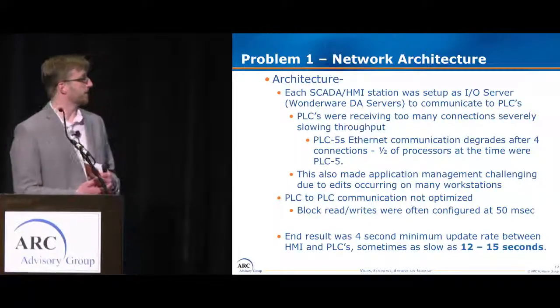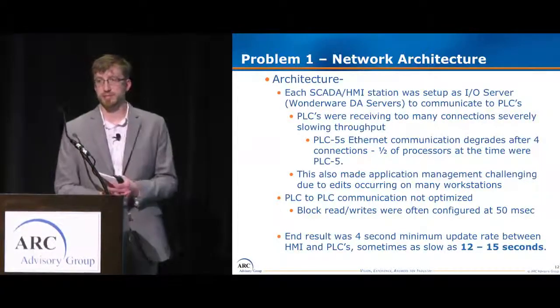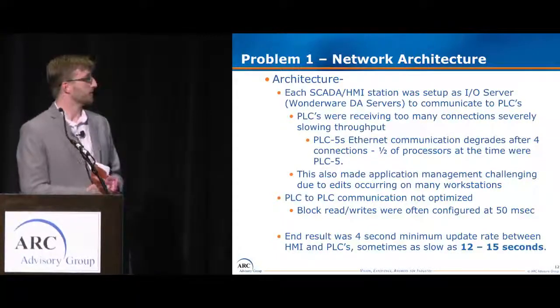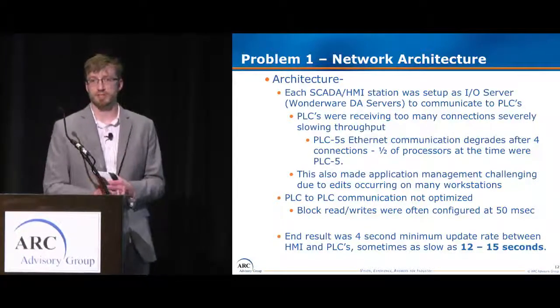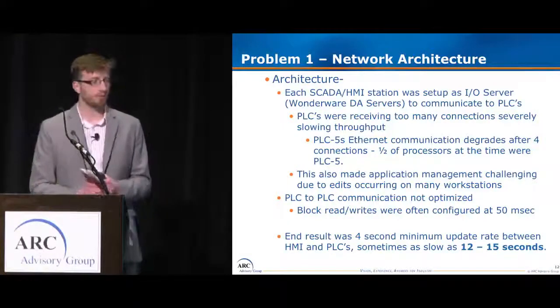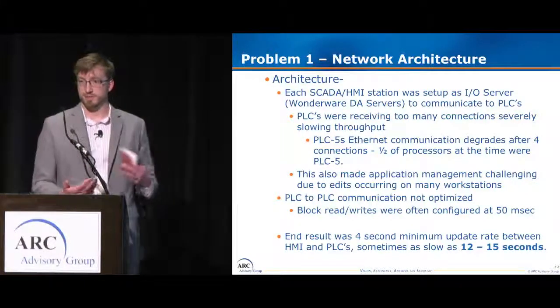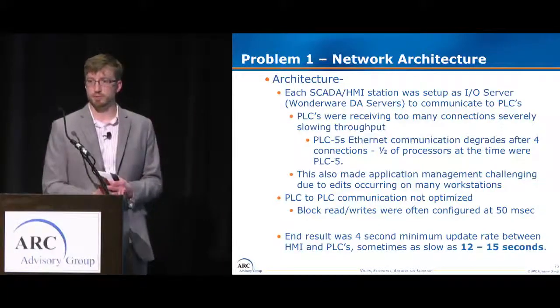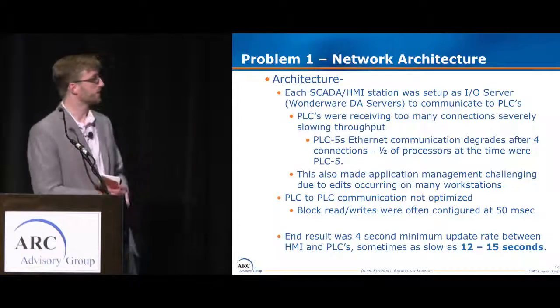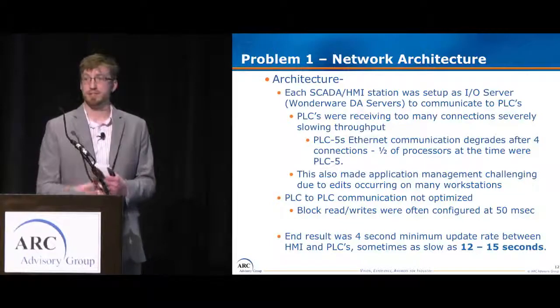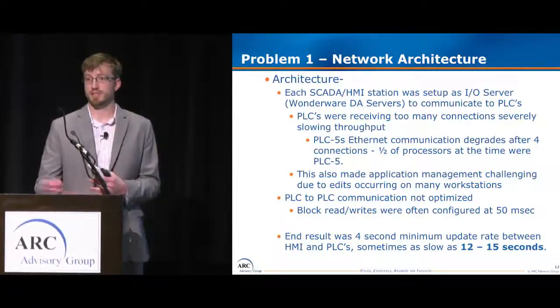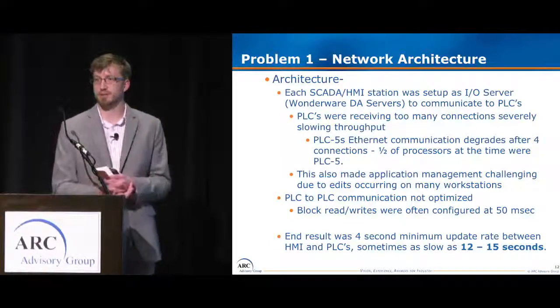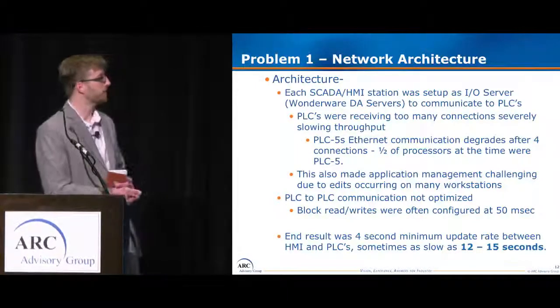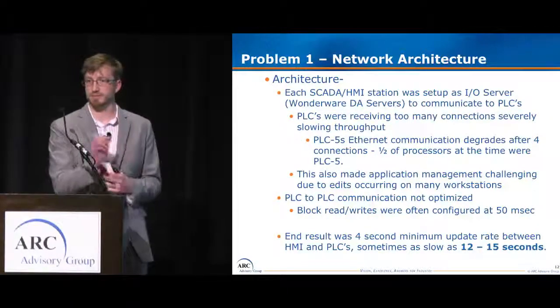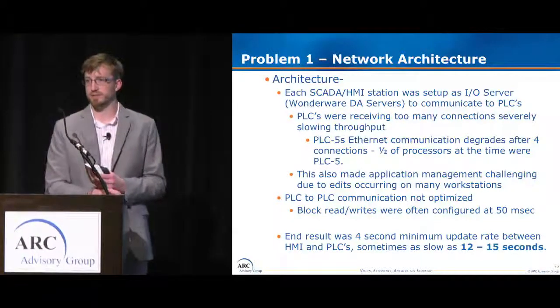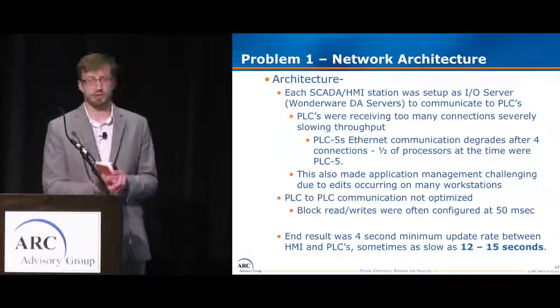There were also a lot of default settings in the PLC to PLC communication, even with the newer technology, where block reads and writes were set to 50 milliseconds, and we had to educate the technicians doing programming in these control systems that we really needed to slow that down to speed it up. It seemed counterintuitive to some of the folks, but when you're pounding PLCs for communication at 50 milliseconds, it starts to slow everything down.